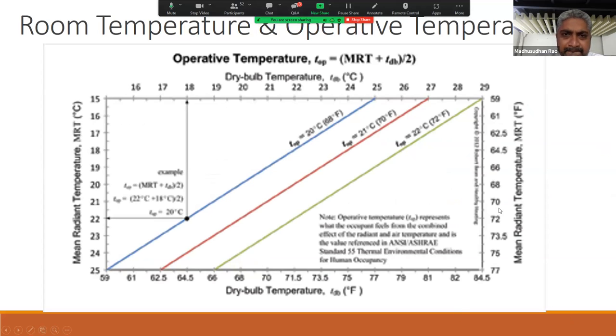Maybe the slide is not clear, but I'll try to explain what this is. You see, all our ISHRAE documentation, ASHRAE documentation also, talks primarily about operative temperature. And many times we make the mistake of equating operative temperature to the dry bulb temperature. But operative temperature is actually a function of dry bulb temperature and the mean radiant temperature. We can approximate it to an average of mean radiant temperature and dry bulb temperature. What is the mean radiant temperature? It is the weighted average temperature of the surfaces that we are exposed to. So in very simple terms, it would be the four walls, ceiling, and the floor, the surface areas and their temperatures multiplied by total surface area, right?